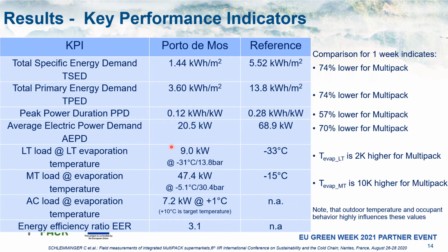If we look at the LT load, we see, of course, a bit of a difference in terms of evaporation temperature. So the MultiPACK system runs with about 2 Kelvin higher evaporation temperature. Due to the system architecture and the monitoring, of course, we have no chance to say something about the load of the reference side, since we have no mass flow meters installed there. For the MT load, we see that there is a huge difference in terms of evaporation temperature. So while MultiPACK is running at -5 degrees C evaporation, the reference system is running at -15. So MultiPACK is running 10 Kelvin higher in evaporation temperature.